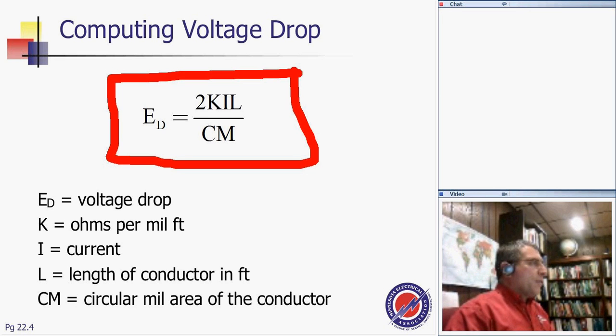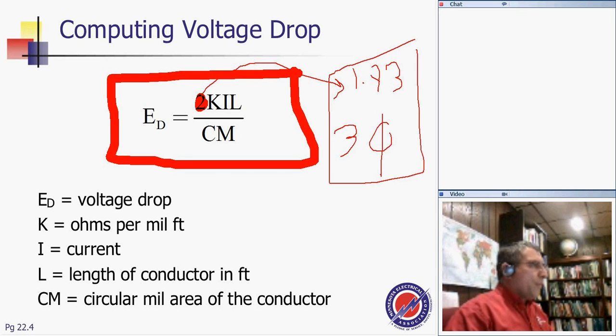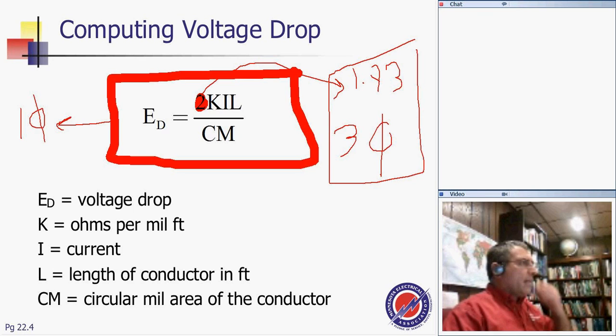The only thing I gave you guys is, instead of the 2, if your system is a three-phase system, the 2 becomes 1.73. Exactly the same formula that we use, except what you're looking at is for a three-phase system, where you put 1.73 instead. Otherwise, 2 KIL over CM is for a single-phase system. Any questions about this formula for single-phase, 2 KIL over CM? If it's three-phase, it's 1.73 instead of 2. Any questions?